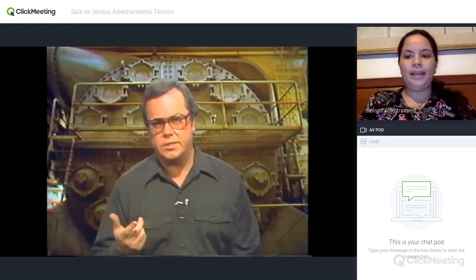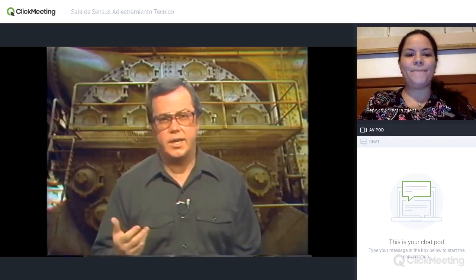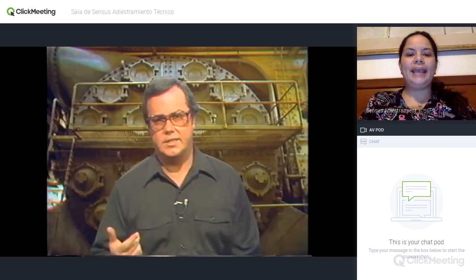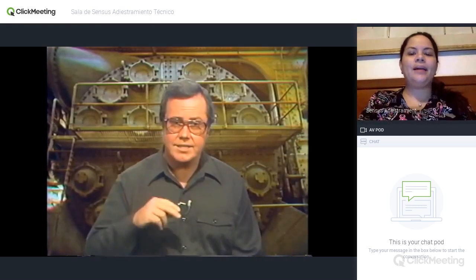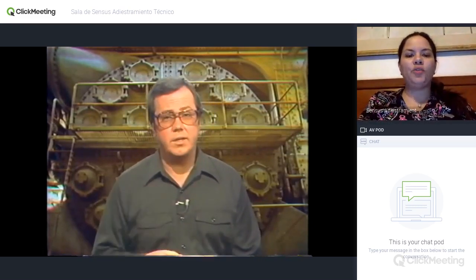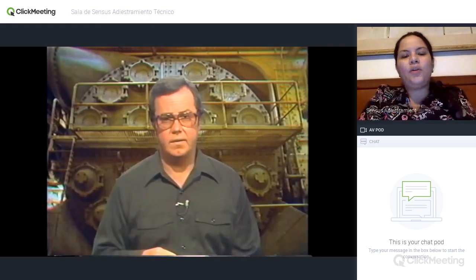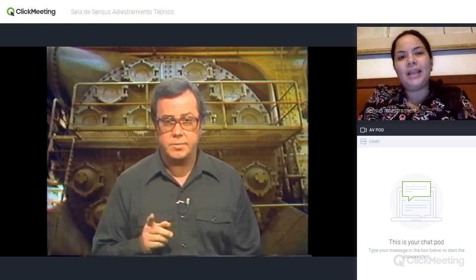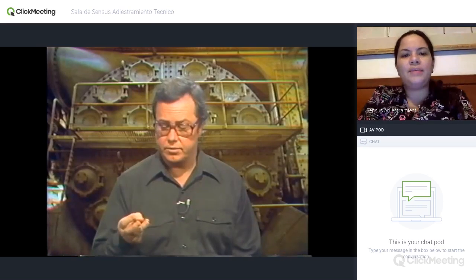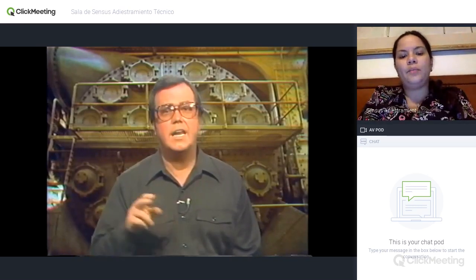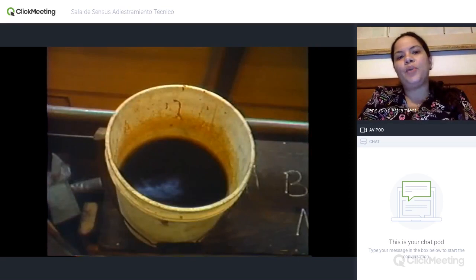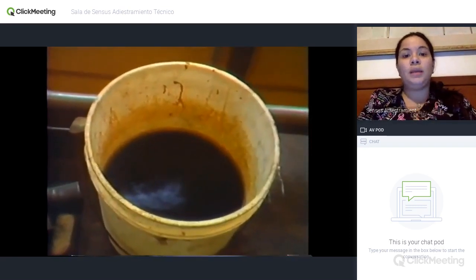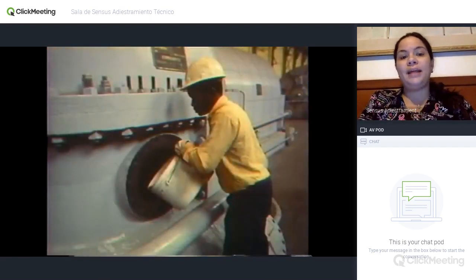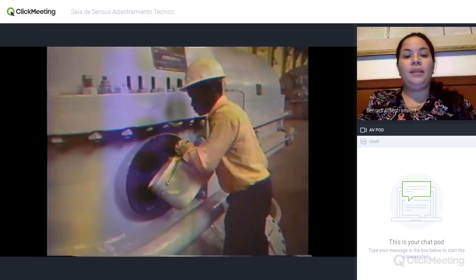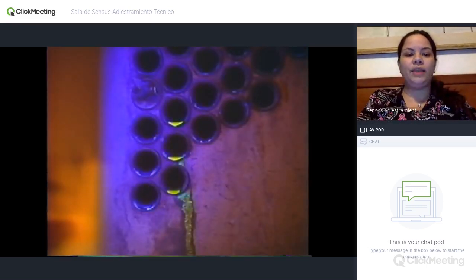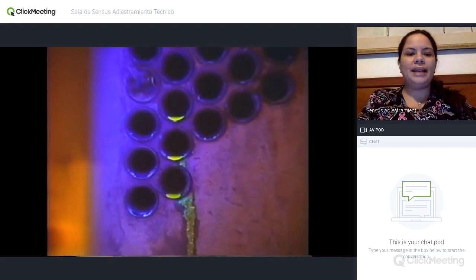To check for leaks in a surface heat exchanger, you may use a dye check or you may perform a vacuum test. Now, these might be done while the component is in service, or they might be performed while the unit's down after it's been cleaned. After cleaning, a visual inspection is done for evidence of corrosion, cracking, or to look for any more blockage. While some heat exchangers are in service, a telltale dye can be added to the water going into them to look for any leaks. This is usually a fluorescent dye that glows when it's exposed to black light, a source of ultraviolet light.